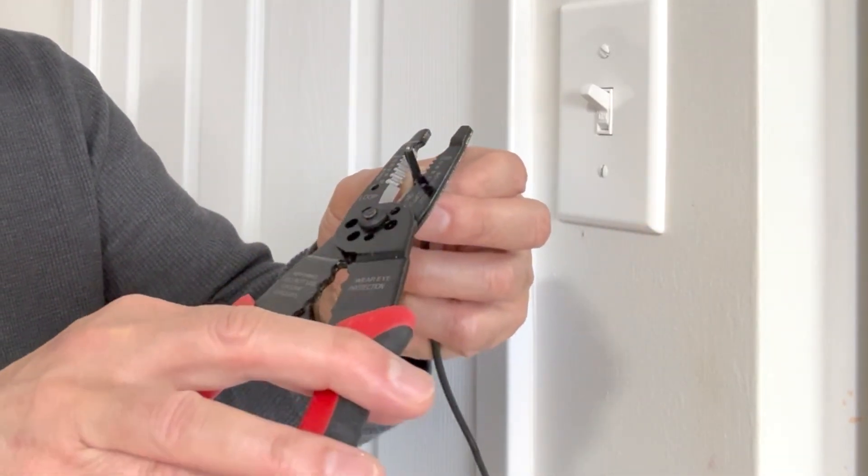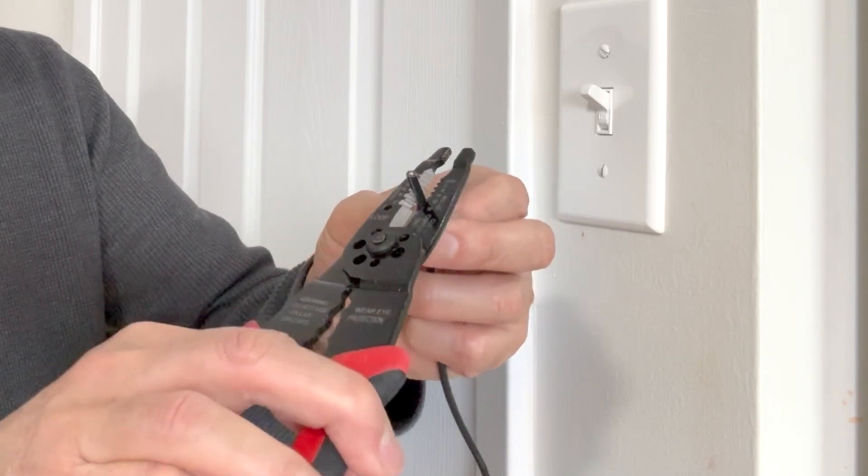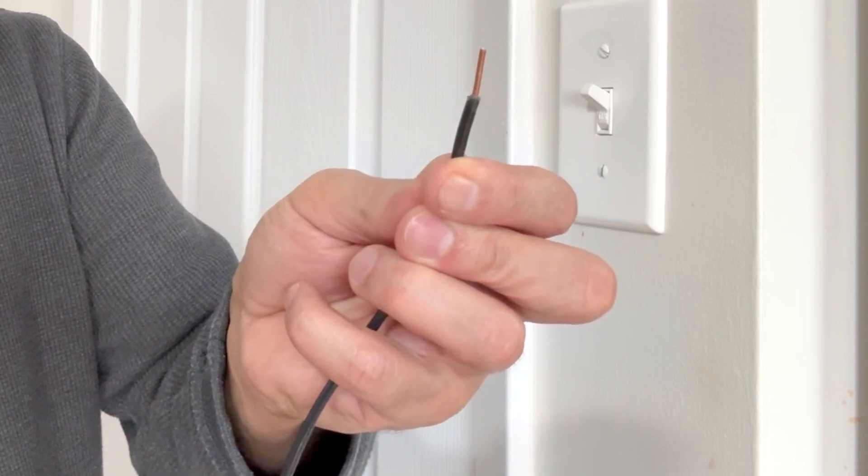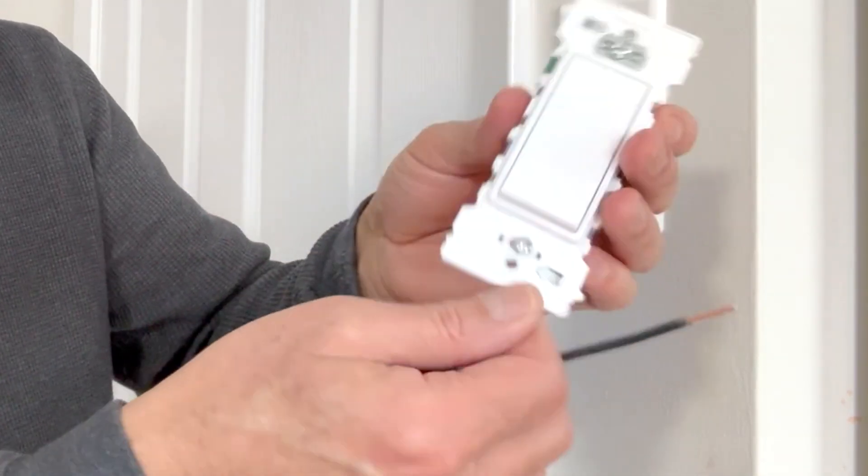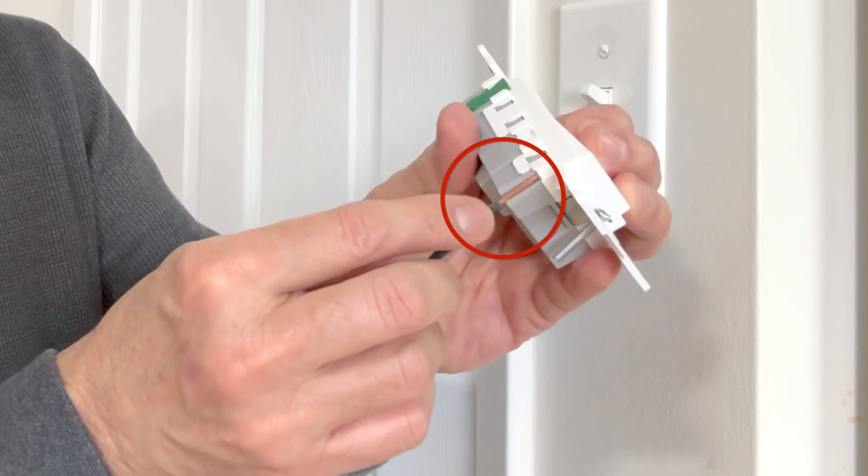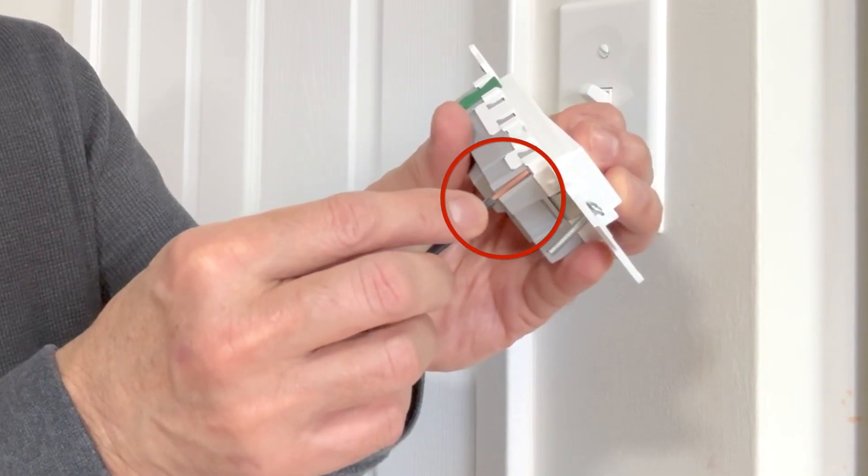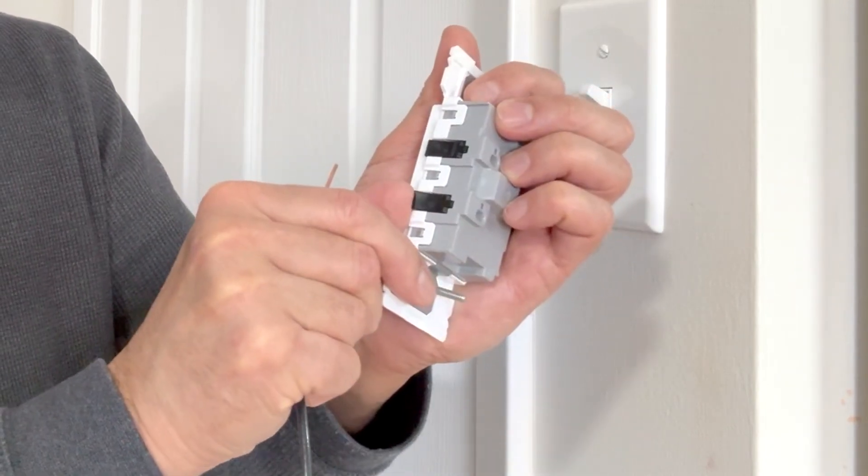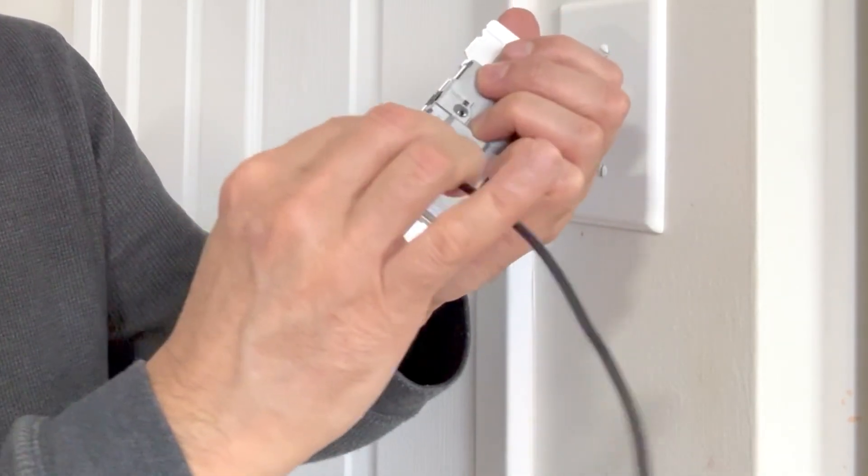Take your stripper 14 gauge wire. So this is about half an inch or you can say five-sixteenths of an inch. Measure it again. This will make sure that we don't have over exposed wire. We don't have extra long wire which is exposed outside the connector. And this is how we can check it.